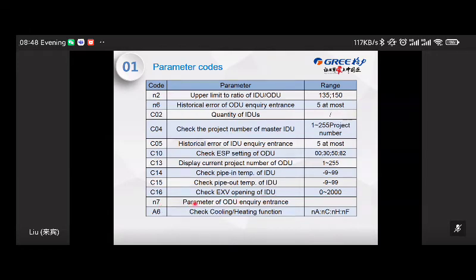Next one is the N7 parameter checking of outdoor units. For outdoor units, there are many parameters such as frequency, current, pressure, and discharge temperature. So you can find more information in this N7 code. Next one is A6, that's the cooling or heating function. You can find whether this unit is in the cooling setting, heating setting, fan setting or heat pump setting. Maybe some engineers just shield cooling in winter or shield heating in summer. You can find the actual setting for the running mode.